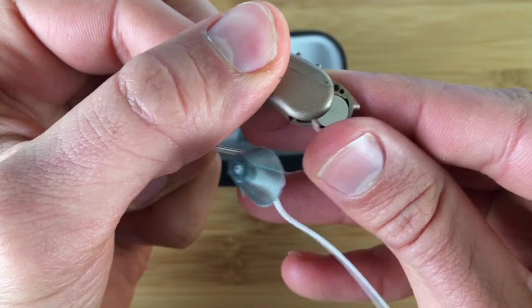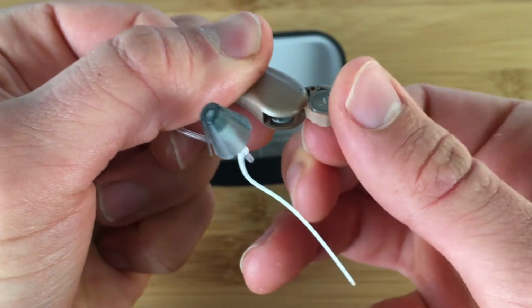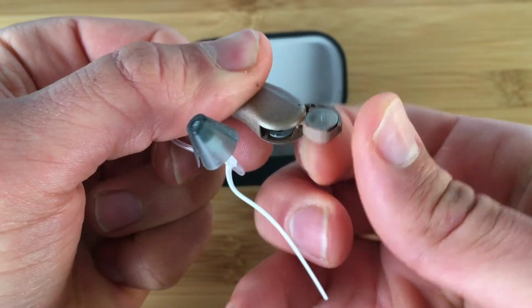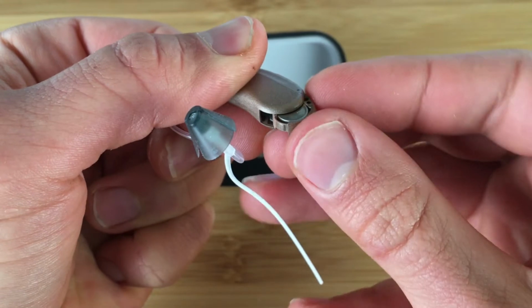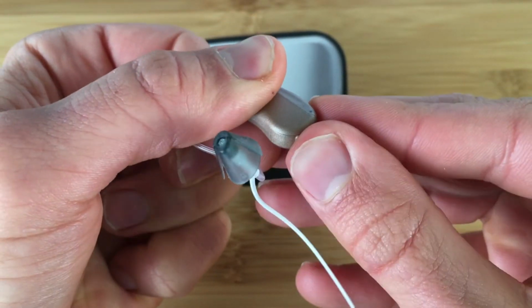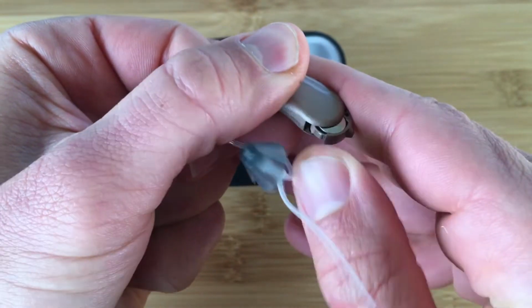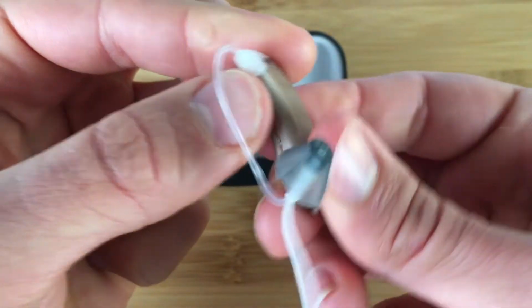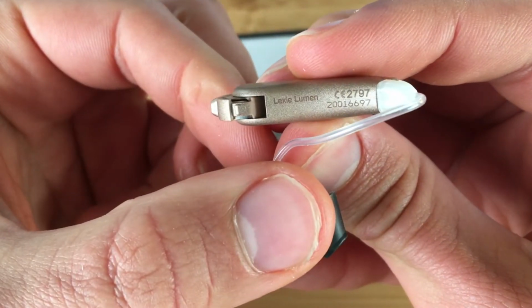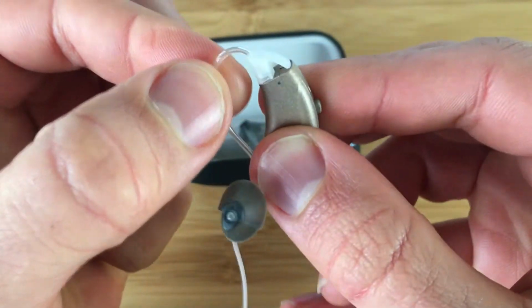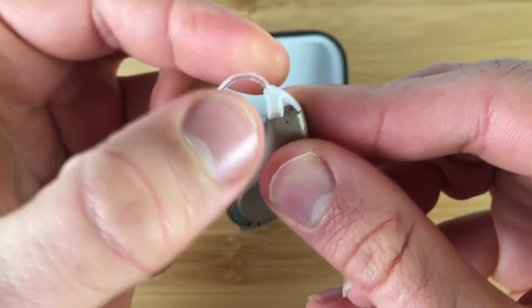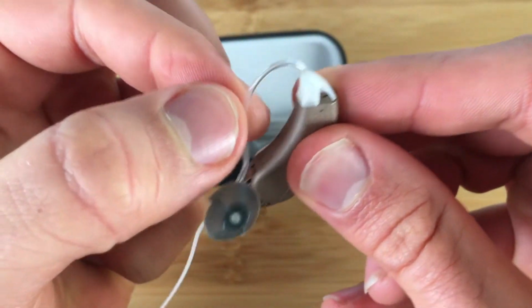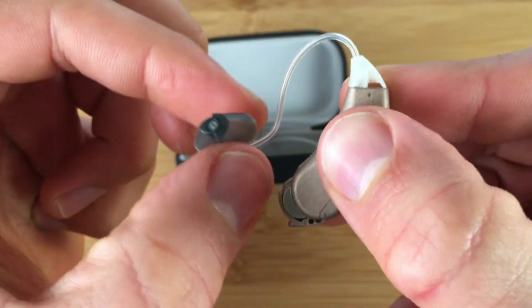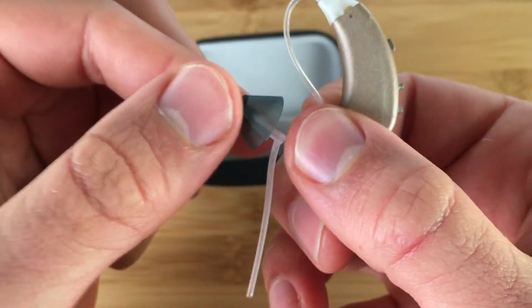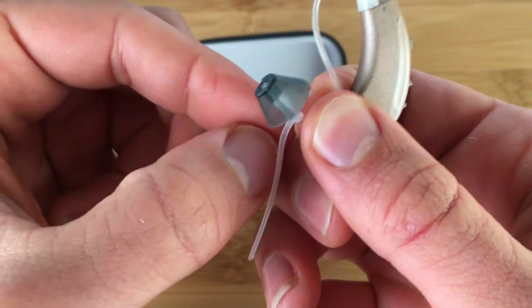At the bottom, this is the battery door. It uses a standard size 312 battery that can be taken out and replaced. And that battery door needs to be closed for the hearing aid to turn on. It all looks good. You can see there Lexie Lumen. And then this part is called a slim tube. This is the plastic tubing that goes from the hearing aid, pushing the sound through the air in the tube and then into this piece, this rubber tip that goes in the ear canal.